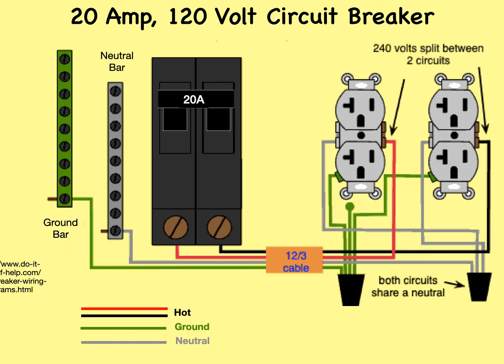This diagram illustrates the arrangement for a 20 amp, 120 volt, double receptacle circuit with a shared neutral wire. This arrangement is typically used in a kitchen or over a workbench where 2 separate appliance circuits are needed in close proximity to each other. Notice that the breaker is a gang breaker, which means that it switches or trips both circuits at the same time. This arrangement is absolutely protected, but can supply a total of 40 amps from a 20 amp breaker, provided that the load is evenly split between the 2 receptacles.